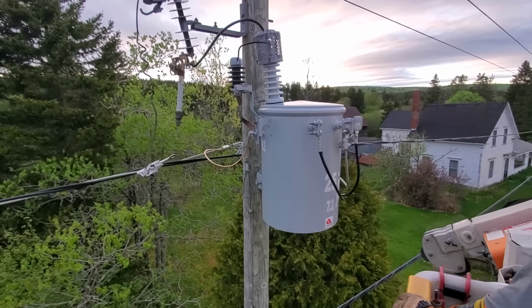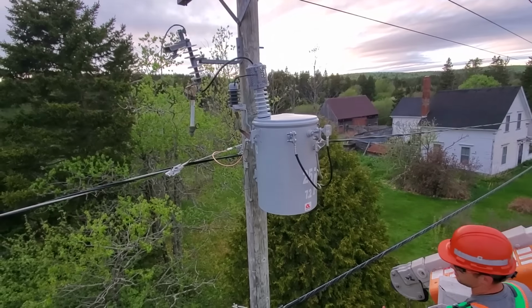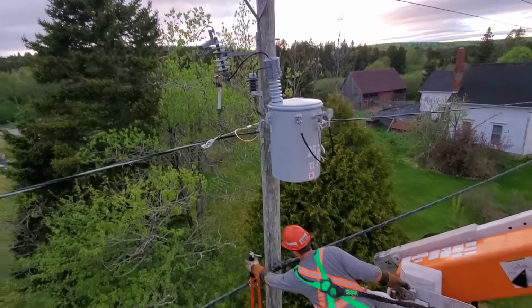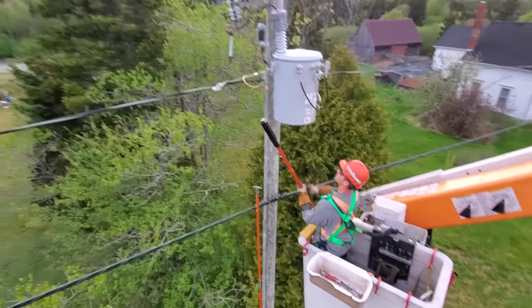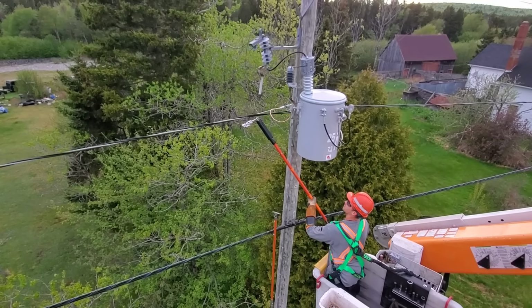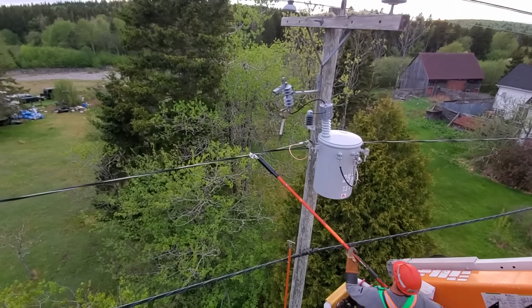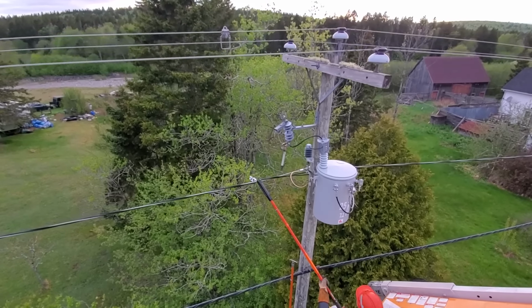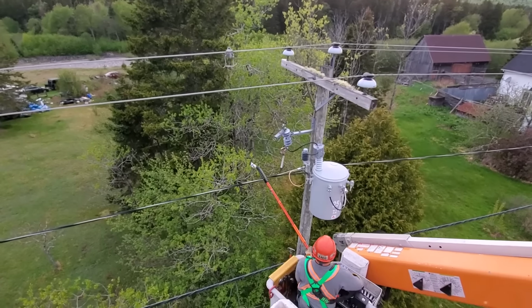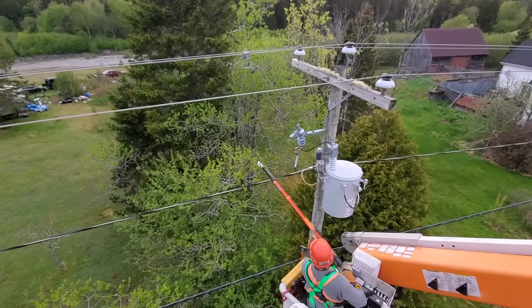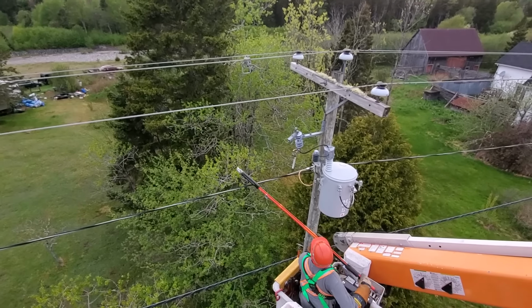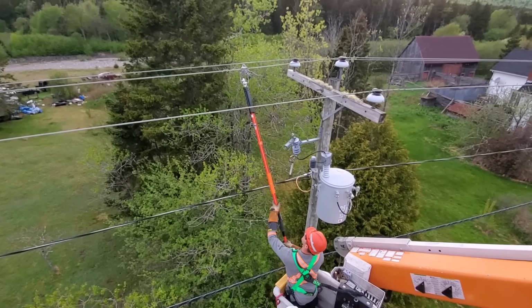So the job's pretty well complete. Secondary leads are back on, primary's back on. He's getting his hot sticks using the 6-foot grab ball. He can safely tap that on. There's no risk of that fuse blowing yet. However, when he closes the fuse, he is going to use a double stick to give himself that 12 feet of clearance.